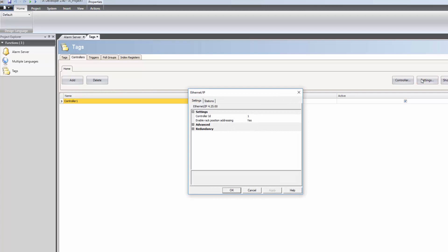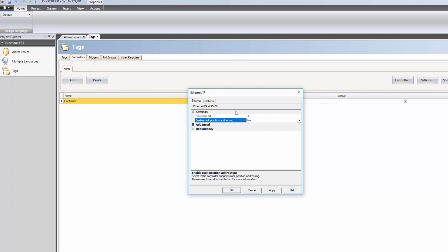When communicating with Micro 800 controllers, the Enable Rack Position Addressing should be set to No. In the Stations tab it is possible to define the IP address that the driver should connect to — in this case 192.168.11.40.